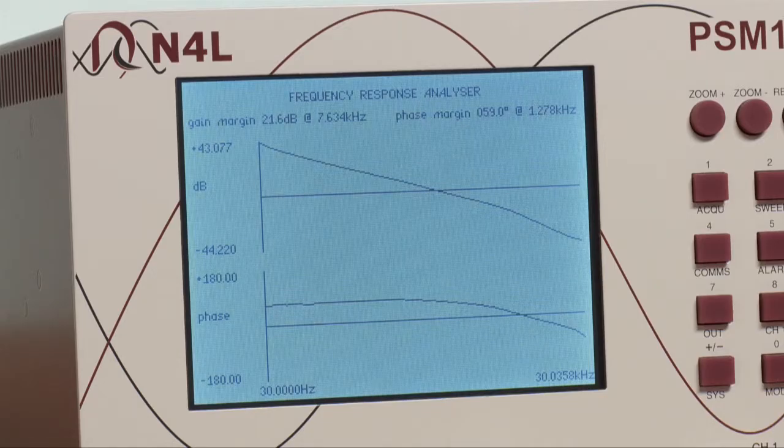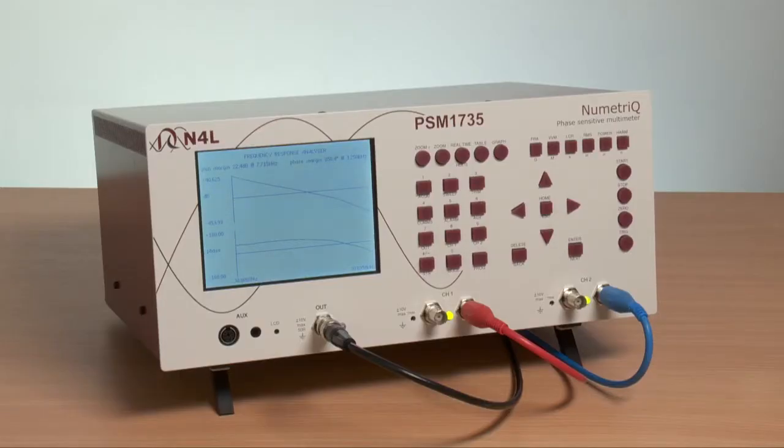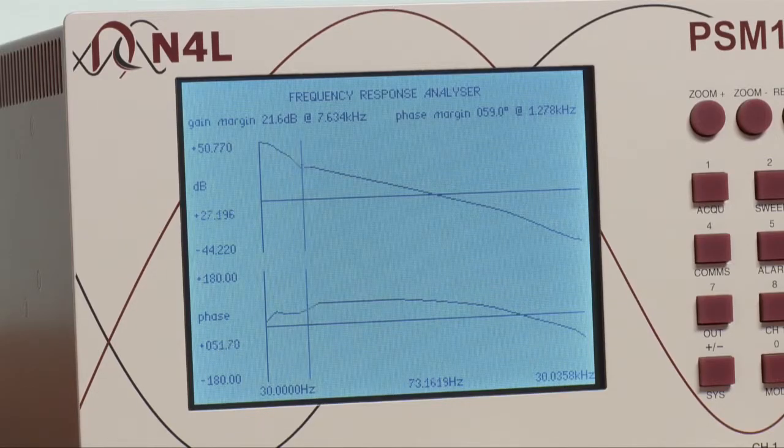If we now change the load, you can see by a re-sweep with a different load that the plot will change quite considerably, which illustrates the significance of load change to control loop analysis.